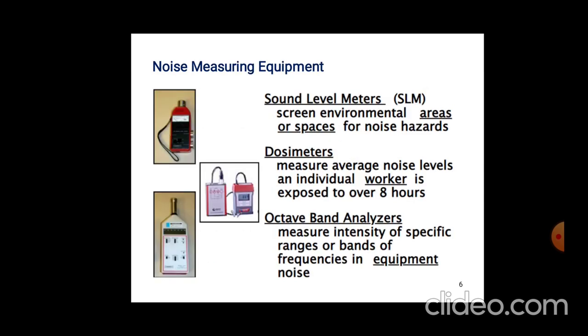The three equipment used for noise measurement are: the Sound Level Meter (SLM), the Dosimeter, and the Octave Band Analyzer. The SLM is used for screening environmental areas or spaces for noise hazards. The Dosimeter measures the average noise level that an individual worker is exposed to over eight hours. The Octave Band Analyzer is used to measure the intensity of specific frequency ranges or bands in equipment noise.